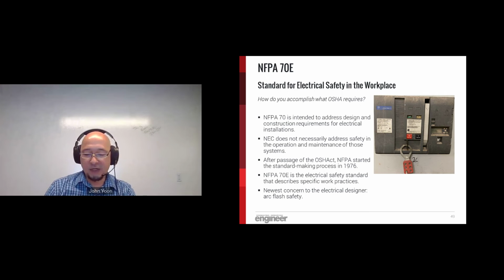The NEC is primarily design and installation, and 70E is primarily operation and maintenance. But on the operation and maintenance side, when we think about safe work practices, the best way to ensure safety when maintaining electrical equipment is to de-energize and lock it out. However, there are multiple situations where turning that off is not desirable or feasible. Data centers, hospitals, what have you.